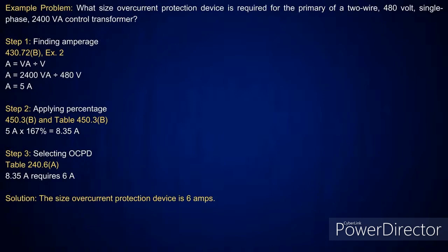So this is very simple. You just get the VA of the transformer, divide it by the voltage, there's your amperage. So we always get the amperage first. And then you're going to go back and look at table 450.3B. Now, this is very simple because I'm just doing the primary only here, because we're talking about a primary 2-wire transformer. You go over and you look at currents less than 9 amperes. Then you look at the next column. It says currents less than 2 amperes. So I'm between 2 and 9 amperes, right? So if I come down and I'm doing primary only, it tells me take it at 167%.